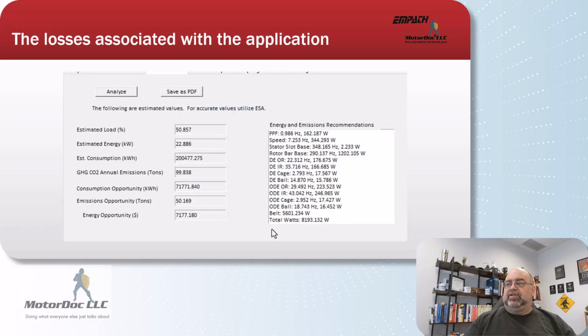The loss associated with the application, now this is where we were detecting the problems. The belted application, because of the improper setting, was 5.6 kilowatts, and then the higher readings here in watts in the OR and IR, outer and inner race of the bearing versus the other part, indicate it's actually a damaged bearing. Therefore, this is going to have to be worked on, and the losses are to the tune of $7,200 a year and 50 tons of CO2 for that area.